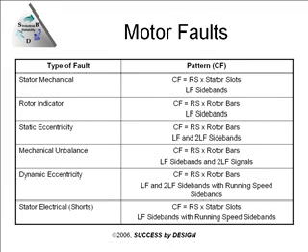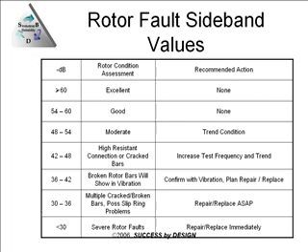With line frequency sidebands, with running speed sidebands around those. Now rotor bar issues have been the number one reason why current signature analysis was developed a long time ago.